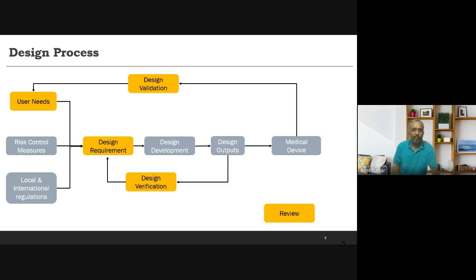Okay. So what is the typical design process? I have tried to take this from ISO 13485 and add a few elements which are not explained explicitly in it. Typically we collect user needs, do risk management, and look at local and international regulations. We club all those things together and then derive the design requirements. This itself is a very iterative process. It's not a straightforward one-to-one mapping where you do these things once and you are done.